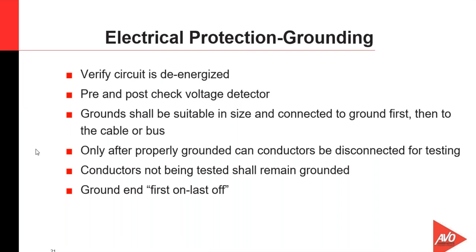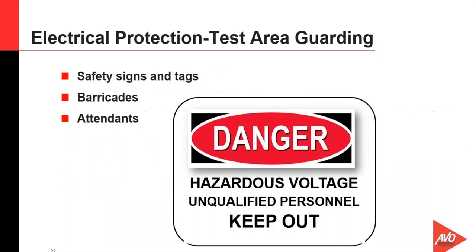The process overall involves verification of the de-energized state, pre- and post-test the voltage detector. These grounds, again, need to be suitably sized and connected to the ground first and the cable or bus last. Only after we properly grounded all the conductors can anything be disconnected for testing. So we want to make sure all the conductors are grounded prior to disconnecting anything to be tested. After testing, then certainly we would reinstall the grounds back. Grounds always go on the ground in first and then come off the phase ends last.